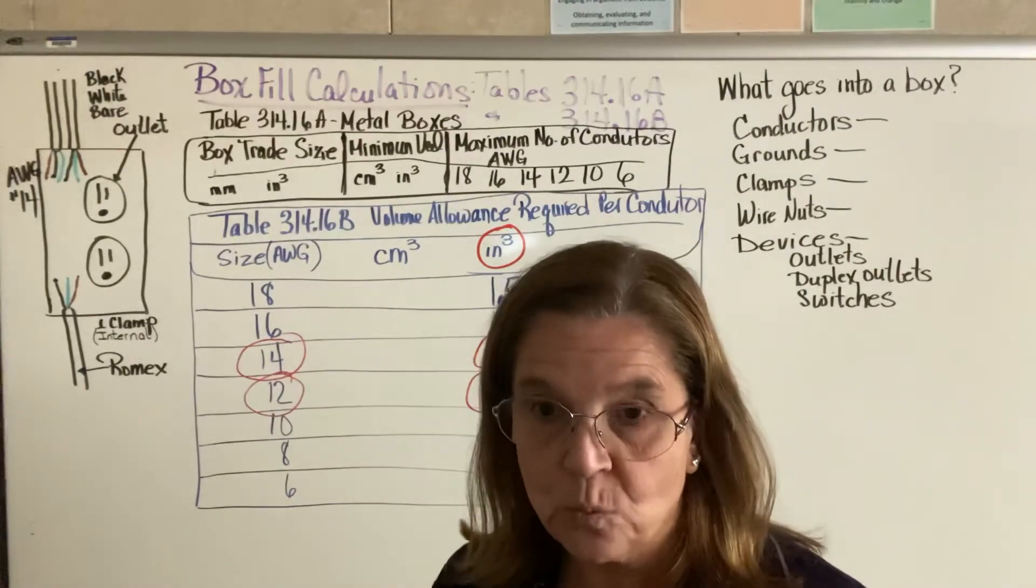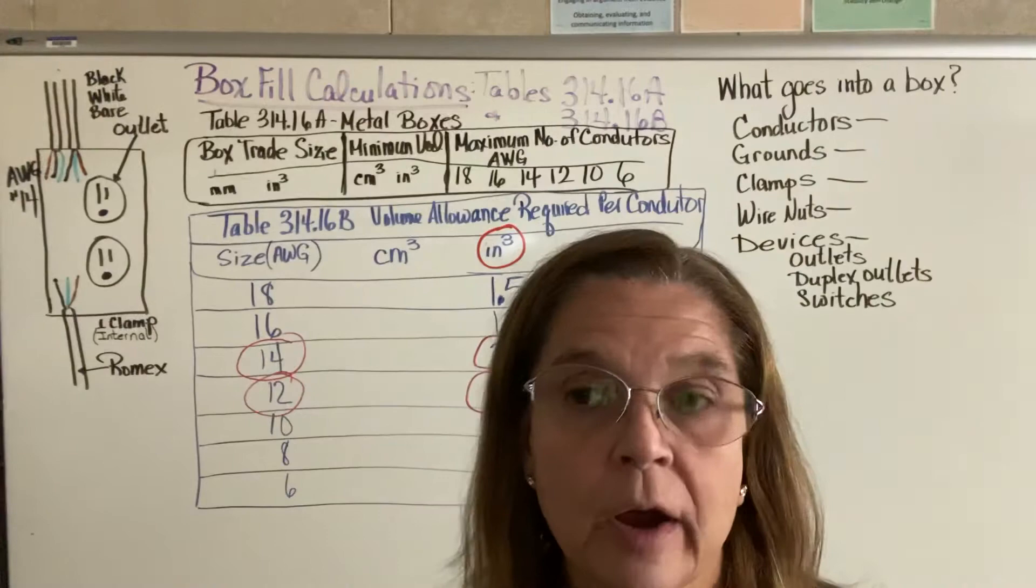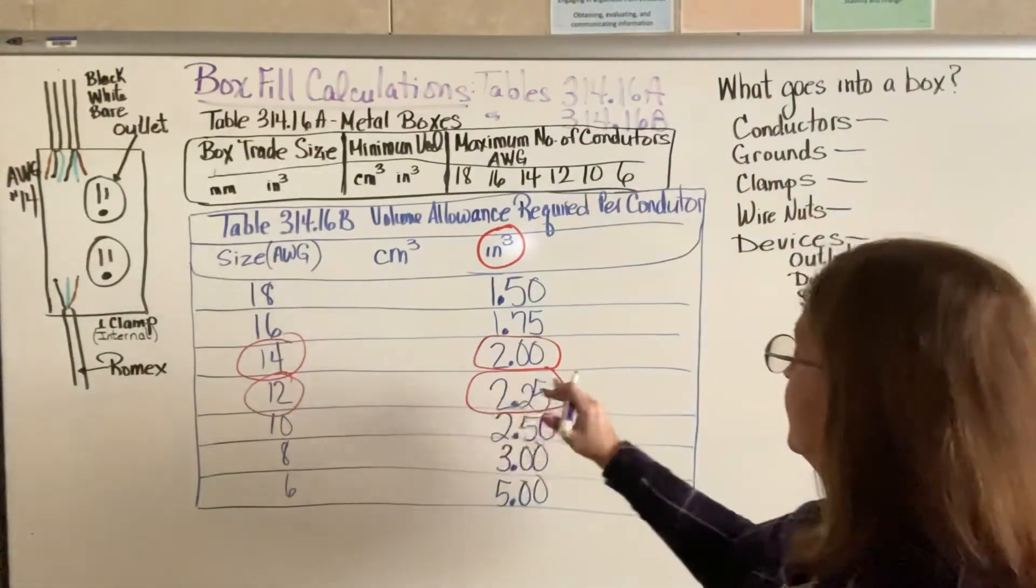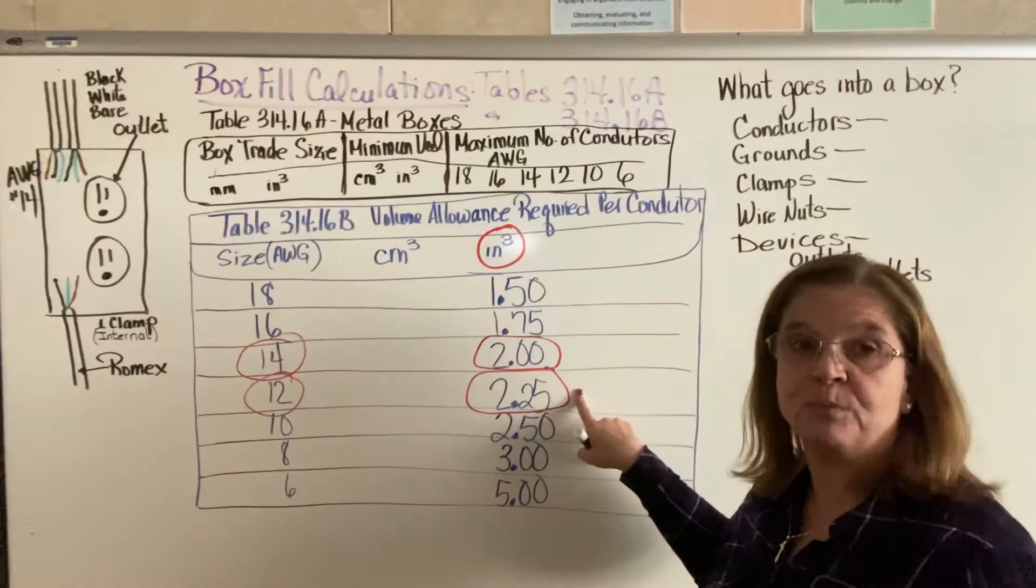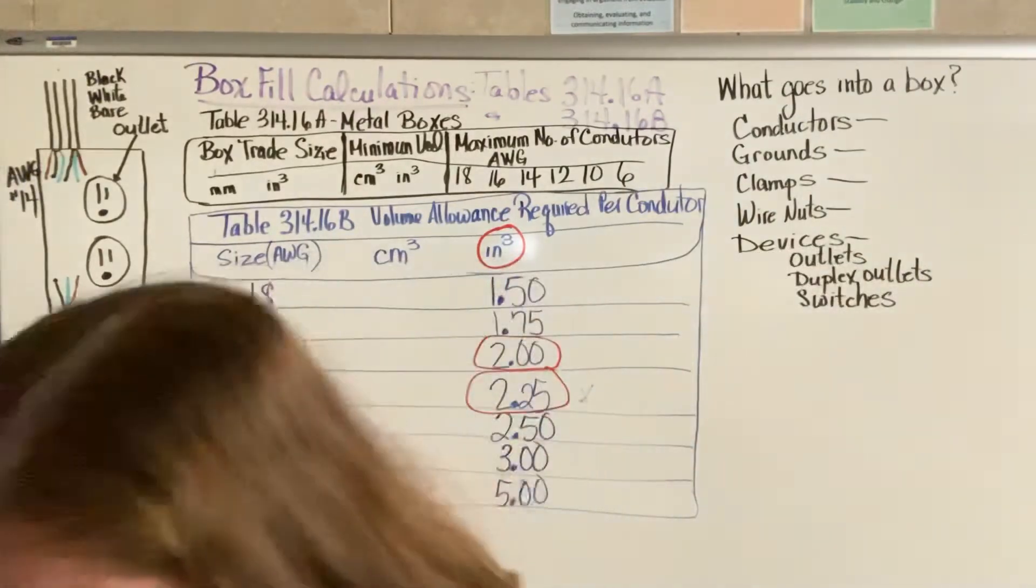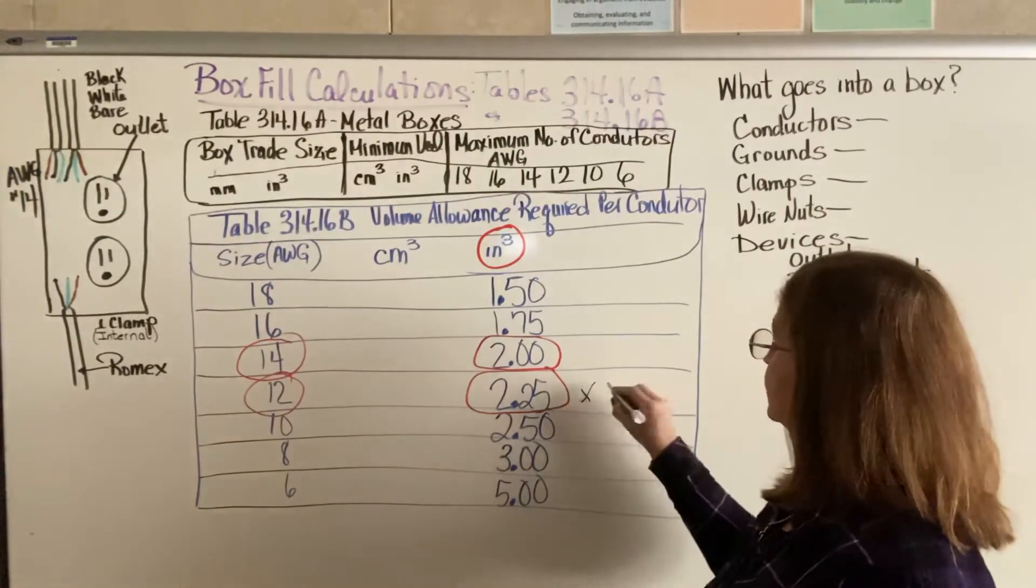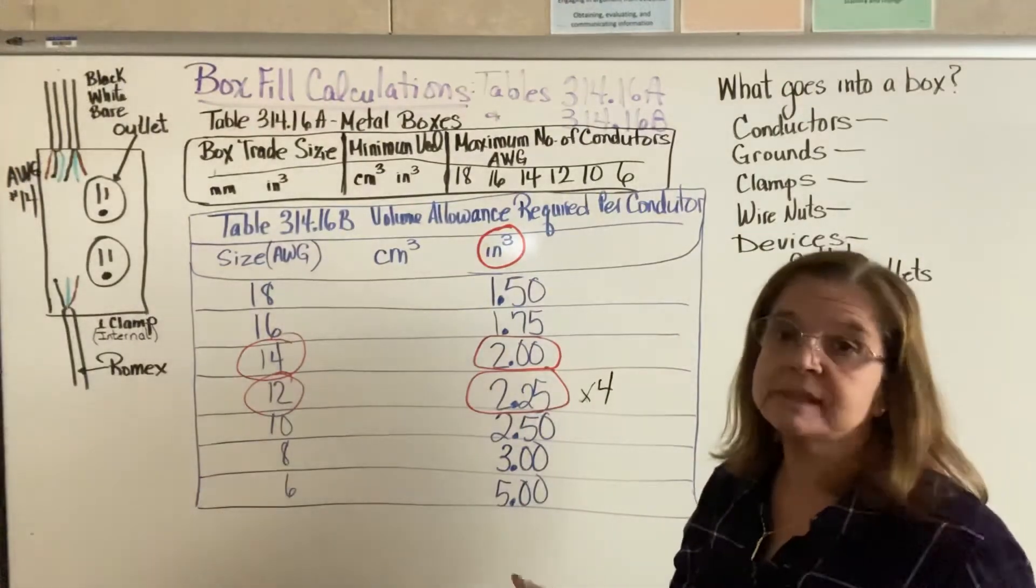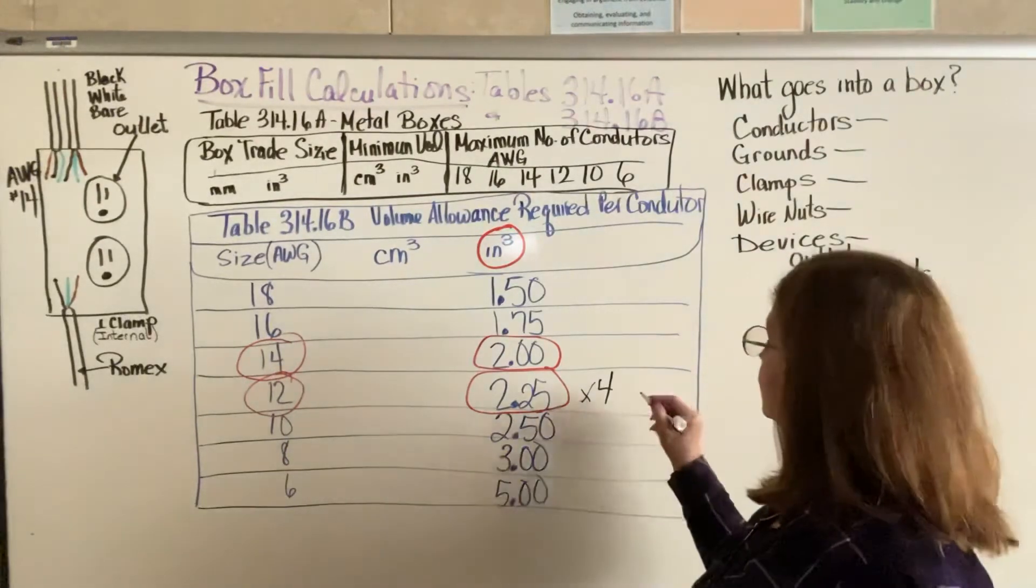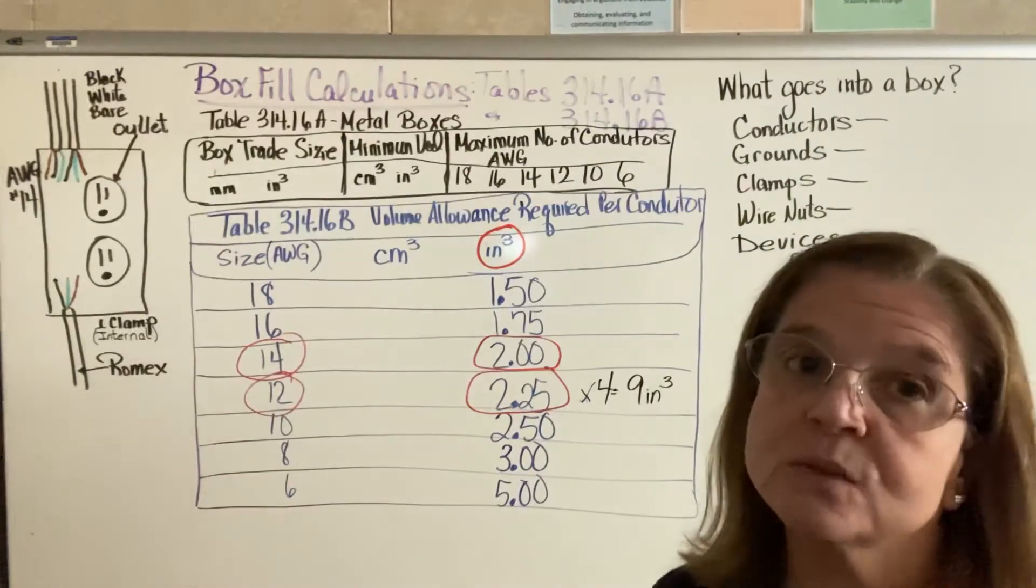So if you're working inside a box and you're looking to put four conductors in that are size 12, the amount of volume just for the conductors, it will be 2.25 times 4 to figure out how much space is being taken up. 2.25 times 4, quickest way to do this is think of it as money. 2 times 4 is $8, .25 times 4 is $1. So this would be 9 cubic inches of space just for the four size 12 conductors.